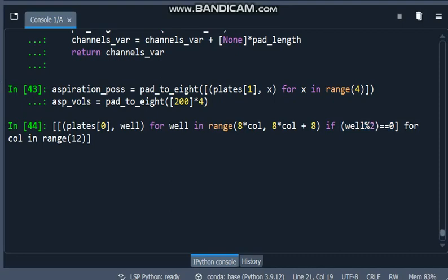We just have one small change to make before we're finished. If we dispense to only even-numbered wells across each column, then each column will have an identical dispense pattern, and that won't produce a checkerboard effect. We need some way of alternating which set of wells gets targeted across each column.